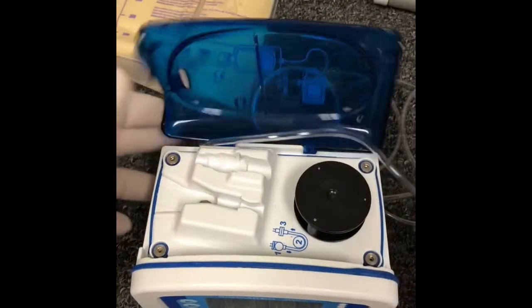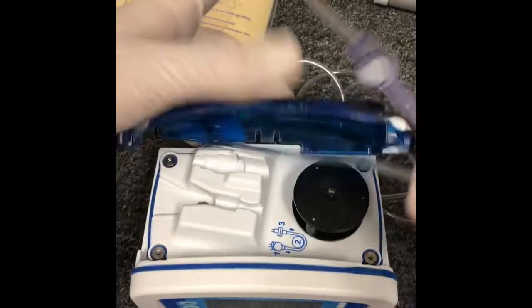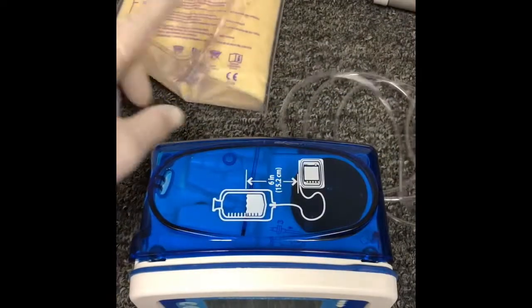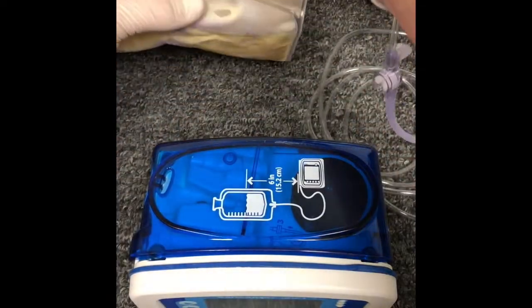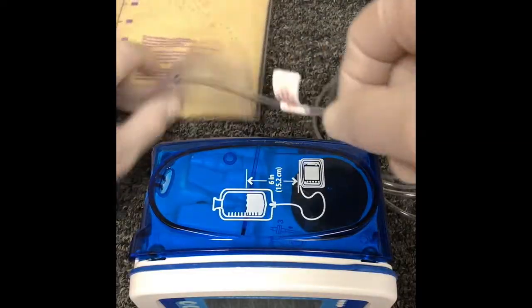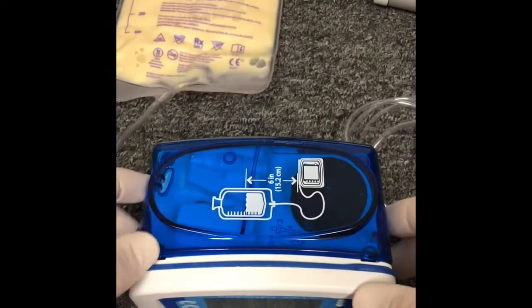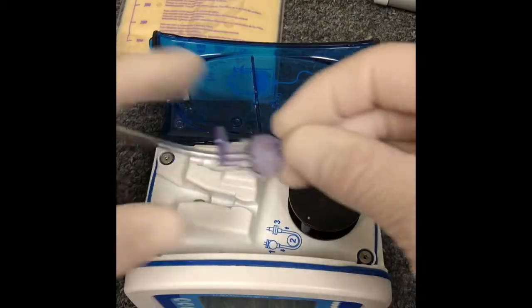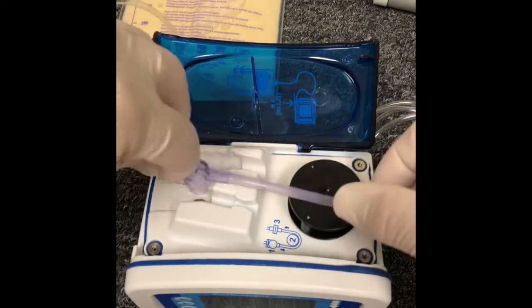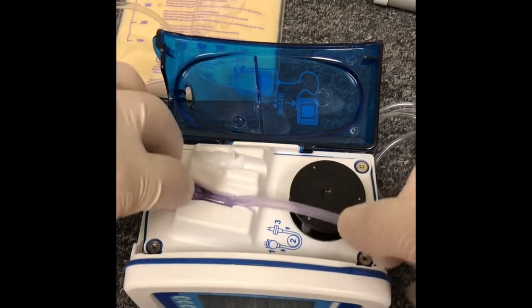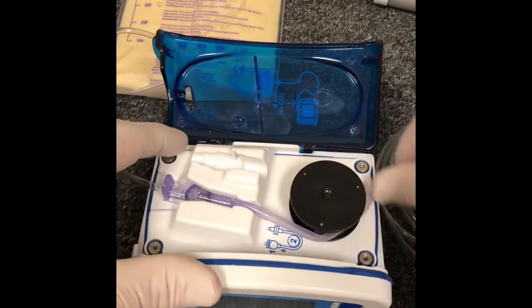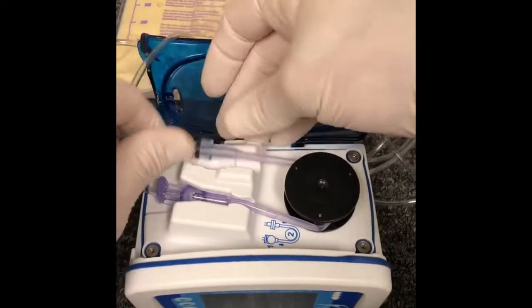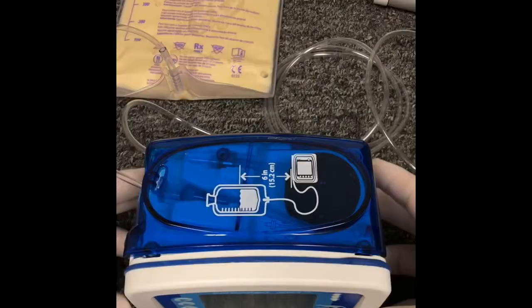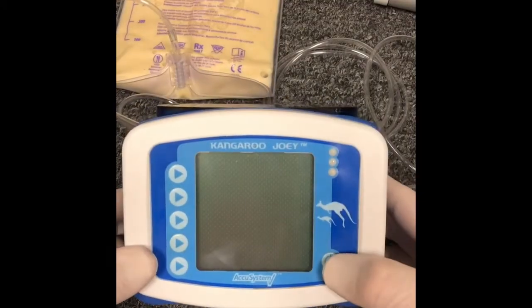As you can see here, there was no flow happening. It's stopped right here. The flow is not going into the tubing at all. That flow stop is stopping it. So let's go ahead and reload this into the pump. Grab it from the little handle, slide it into place, pull it through the channel, around the wheel, and into position, and close that. All right, now let's take a look at the pump's programming.